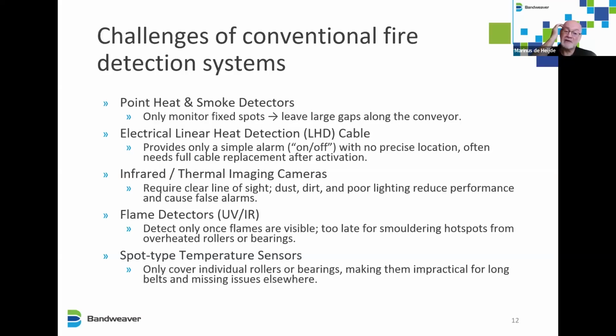Then there are also infrared or thermal imaging cameras. They require a clear line of sight. And at these industrial facilities, there's normally a lot of dust, dirt, and poor lighting, which reduce the performance and can also cause false alarms. So again, it's not very practical. Same thing with flame detectors. They detect only once the flames are visible, which is too late for smoldering hotspots from overheated rollers or bearings.